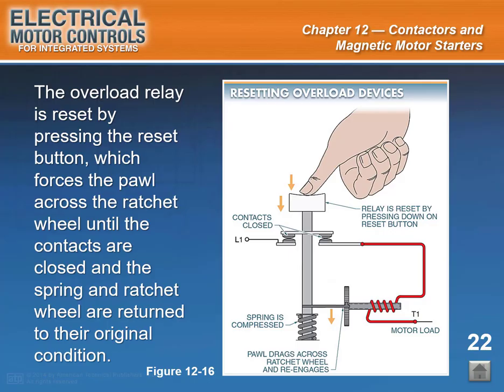Slide caption: the overload relay is reset by pressing the reset button, which forces the pawl across the ratchet wheel until the contacts are closed and the spring and ratchet wheel are returned to their original condition. See Figure 12-16. The cause of an overload must be found before resetting an overload relay. A relay trips on resetting if the overload is not removed. Once the overload is removed, the device can be reset, only requiring time for the solder eutectic to solidify again.